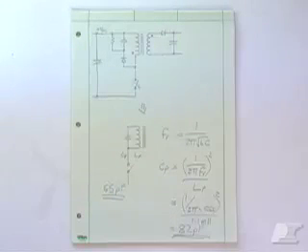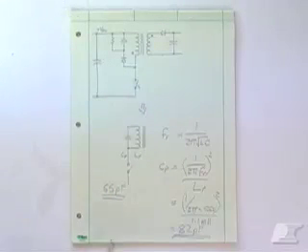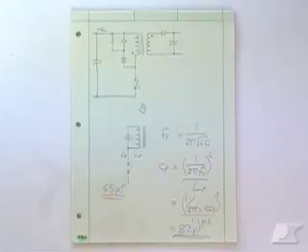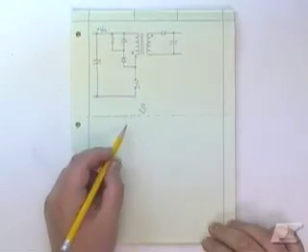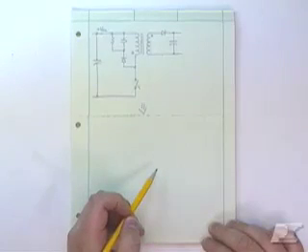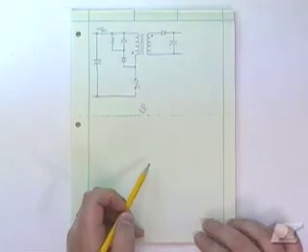Now that we've used the relaxation ring to estimate the value of the primary capacitance, we can go ahead and do something very similar to estimate the value of the leakage inductance. Just after the clamp network has stopped conducting, we measured the frequency of ringing.